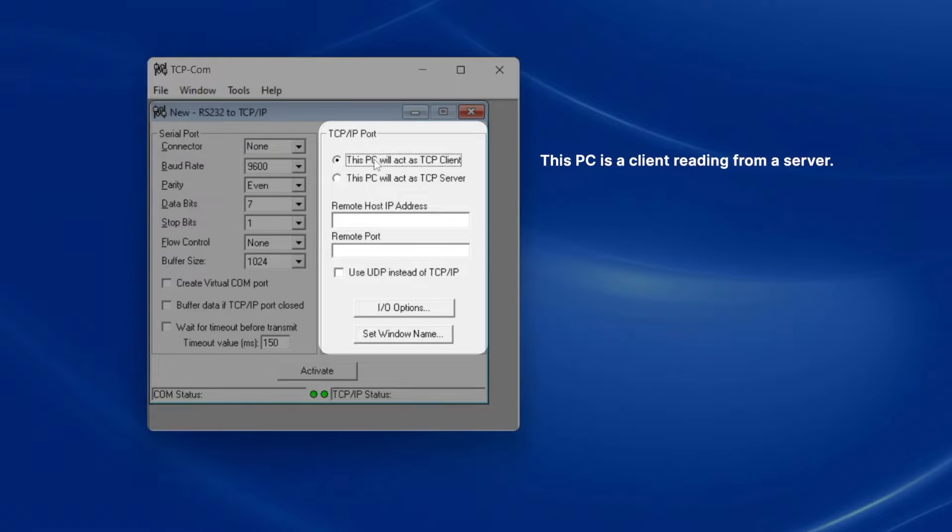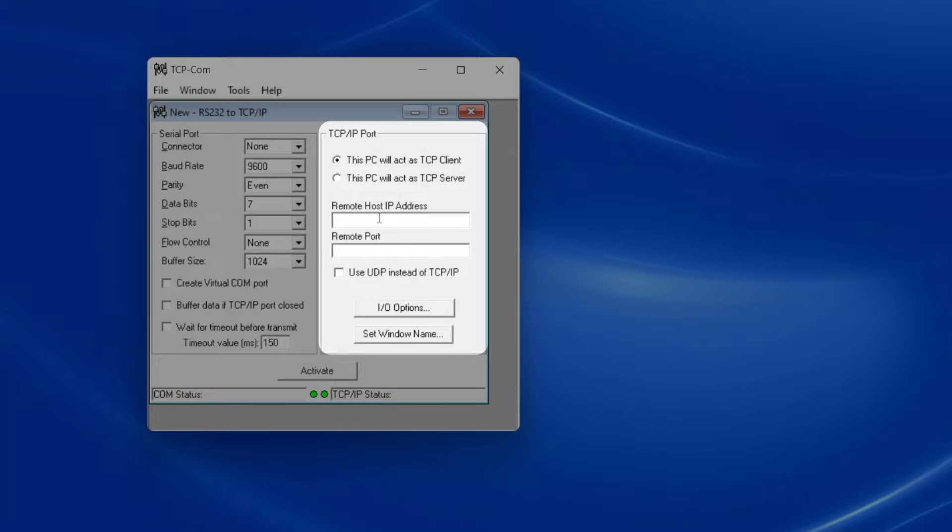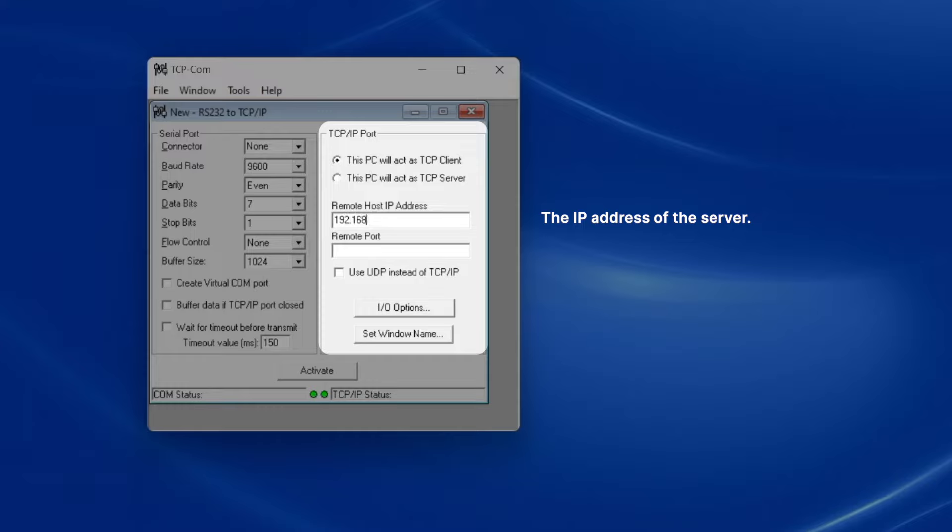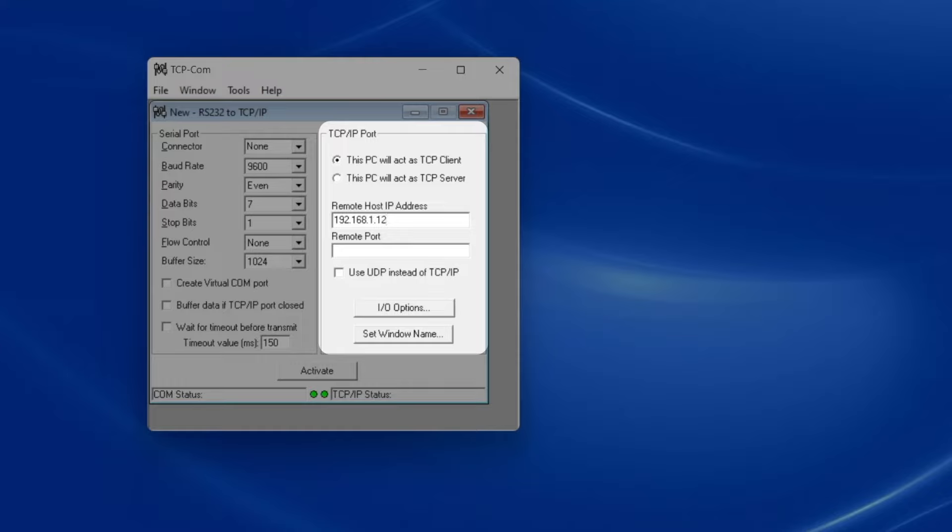Now it needs to know the balance's IP address, along with the port number to use for communication. In my balance's settings, I've already configured the balance to use the IP address 192.168.1.12, so I'll type this into the field remote host IP address.